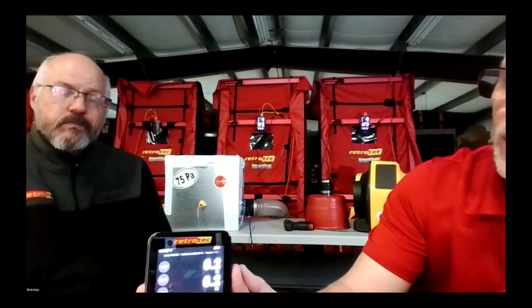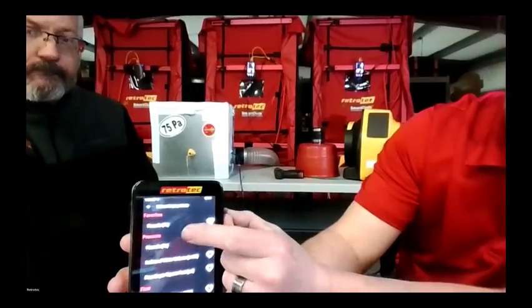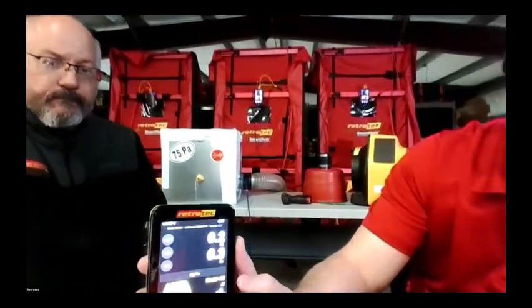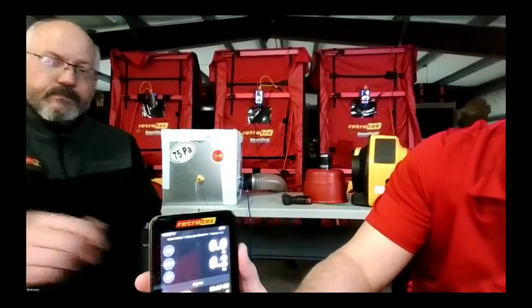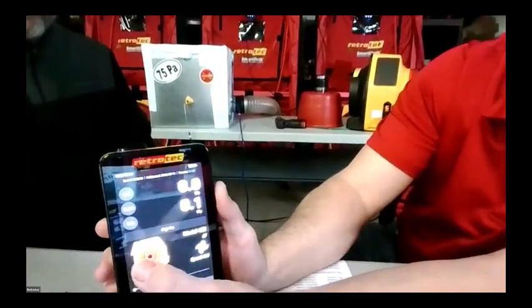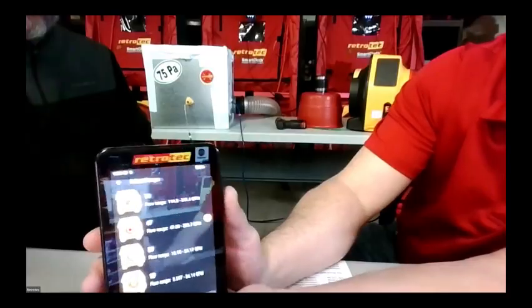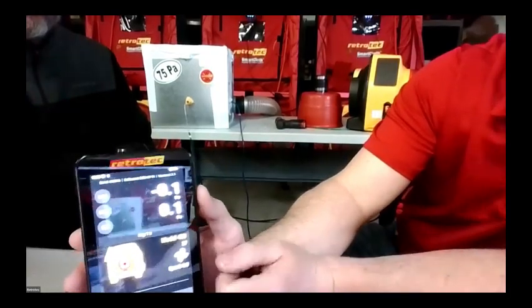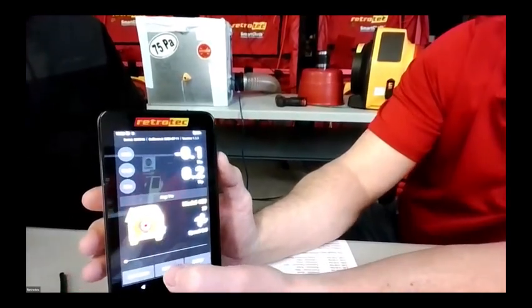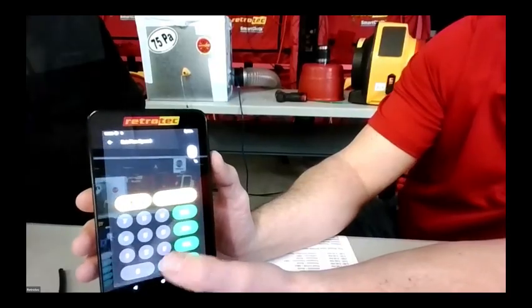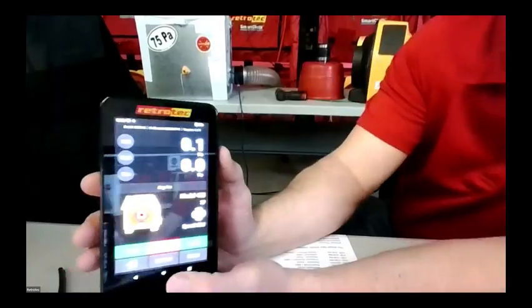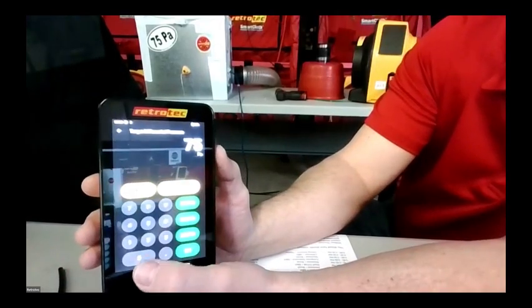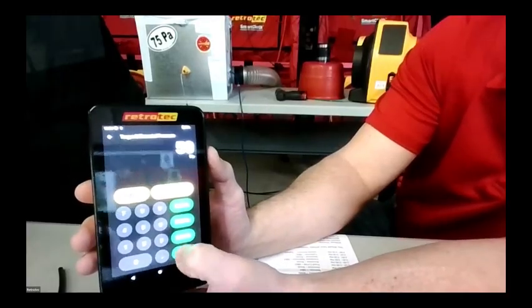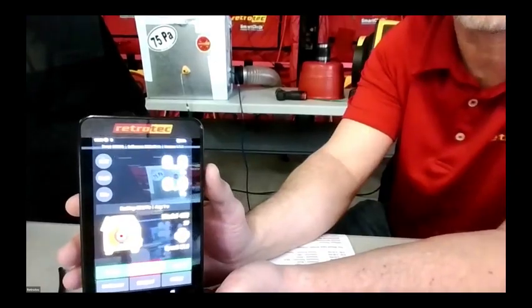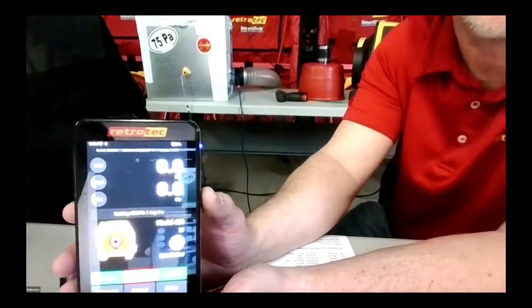If you want to change your units from water column to pascals, you press it. You can do it on either channel. Your favorites are at the top, so we're back to pascals on this one. If you need to change your configuration, you touch the icon of the fan, and you can select your new range configuration. It also tells you what the range is on that. When you set your speed, that's the fan speed, so you can go 25%. That's going to take the fan to 25% and just hold it there. As opposed to set pressure, where you'd be seeking a target pressure. As things change, it will constantly seek the 50 pascals or whatever you have it selected to.